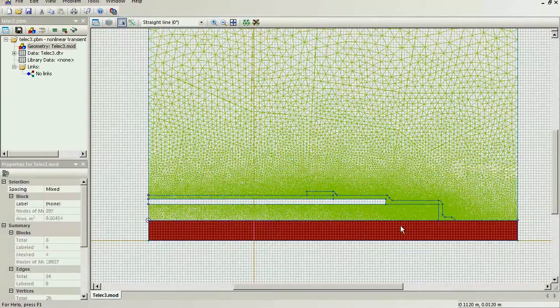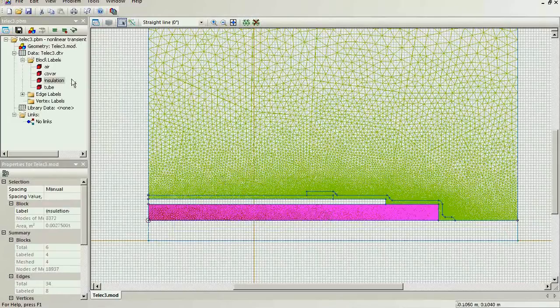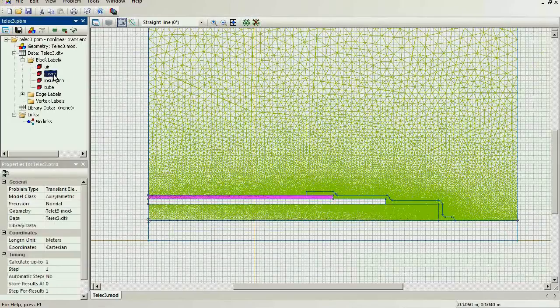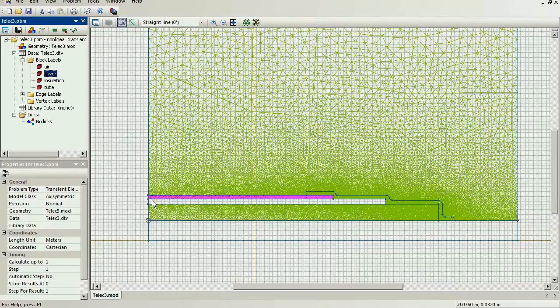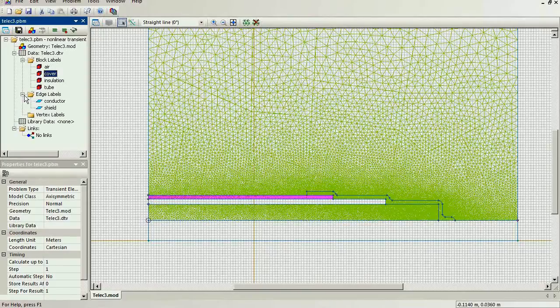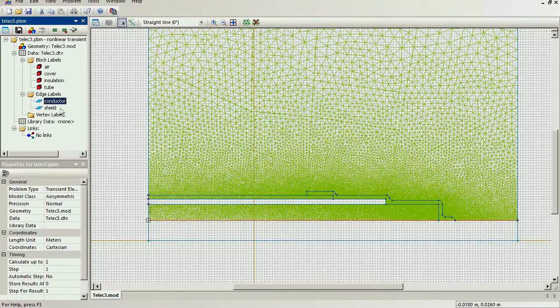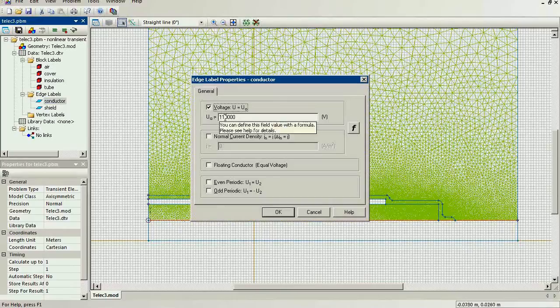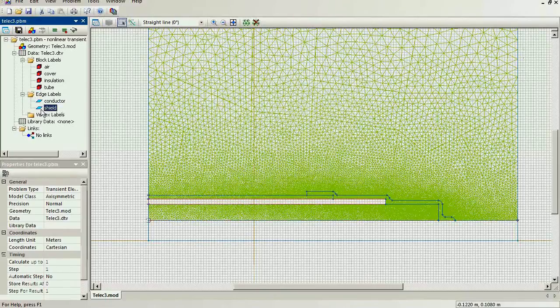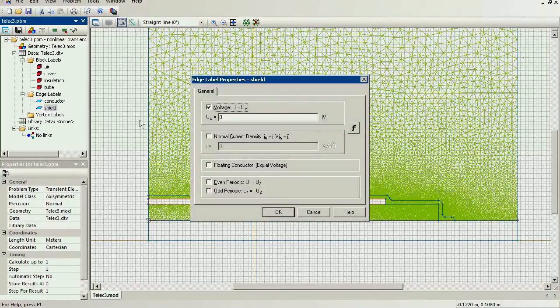This block is the cable conductor. This is the insulation and this is the cover. In an electric problem, we do not simulate the electric field distribution inside the conductors. Instead, on the conductor surfaces, we specify the electric potential of the conductors. For this conductor on its surface, I specify the electric potential of 110 kV. And the shield is grounded.